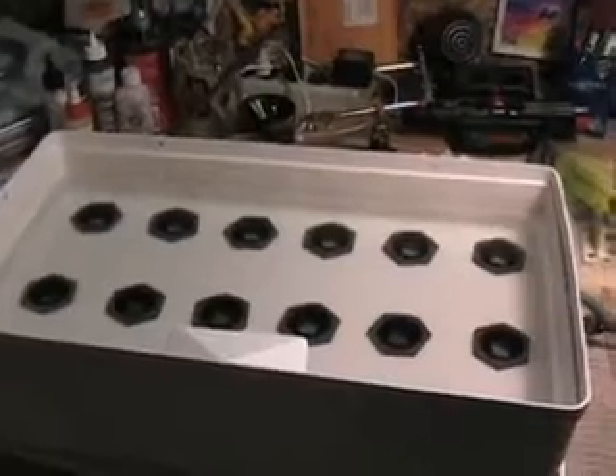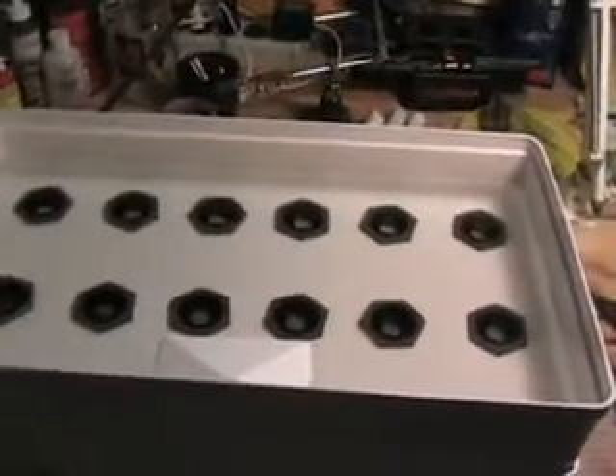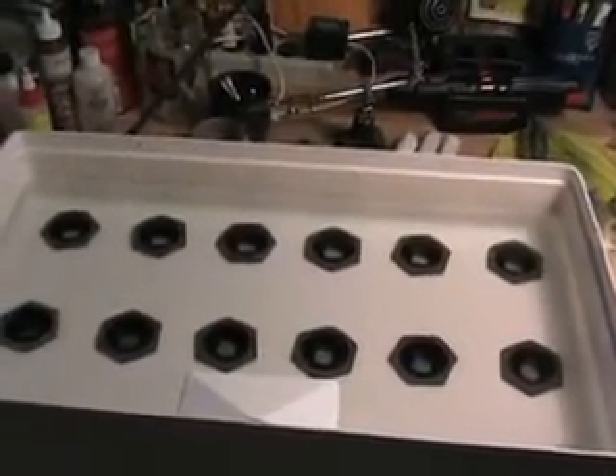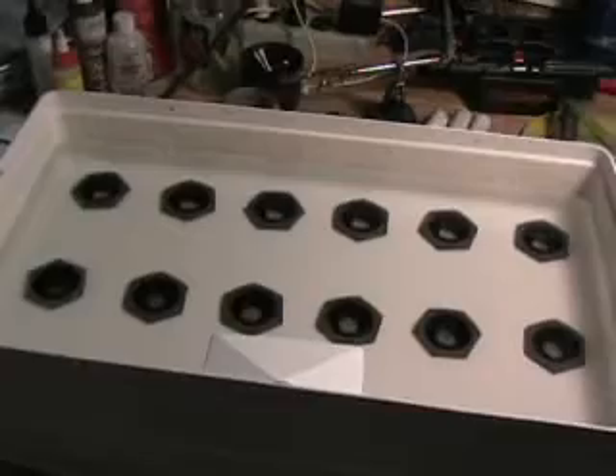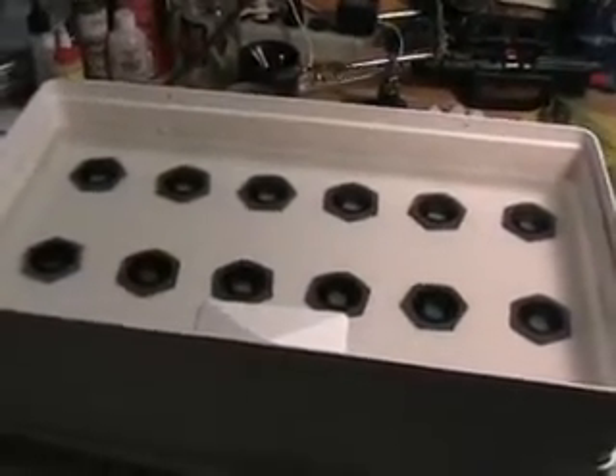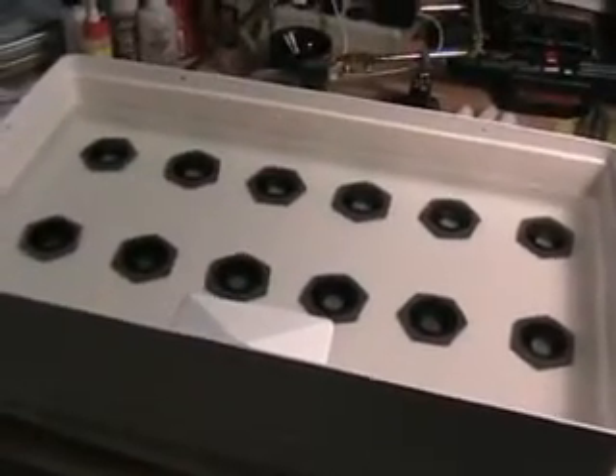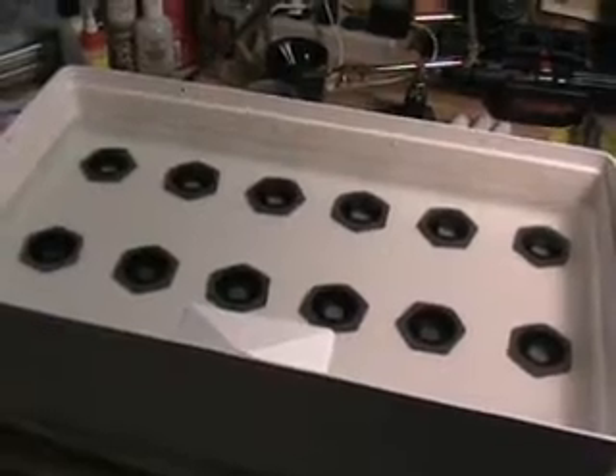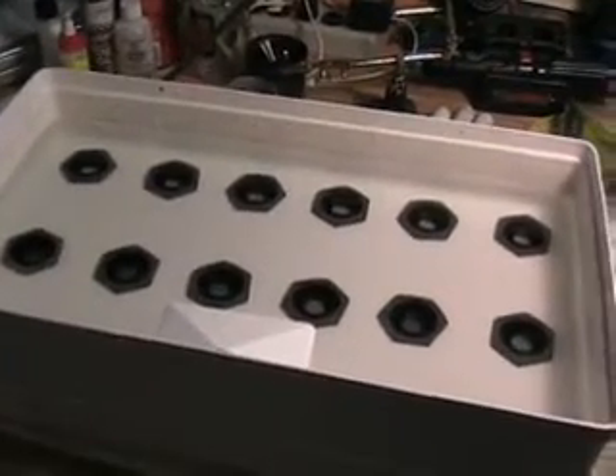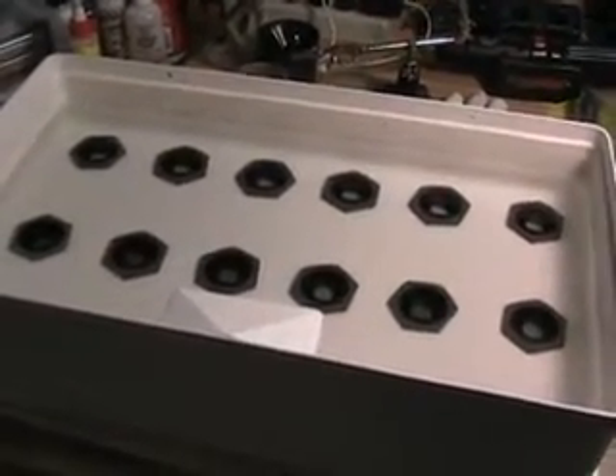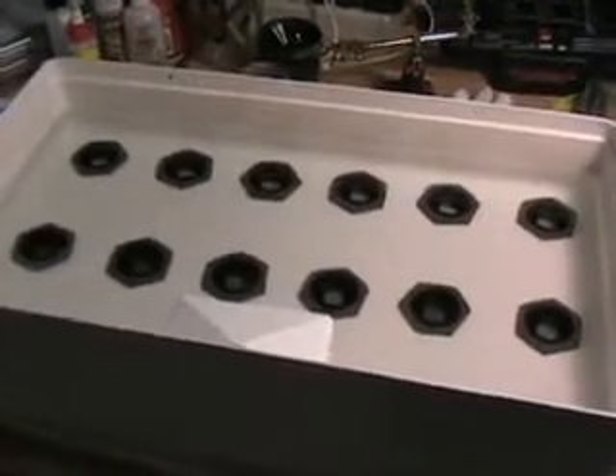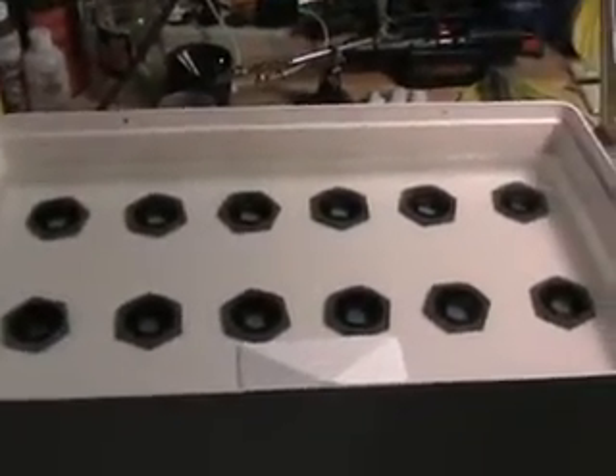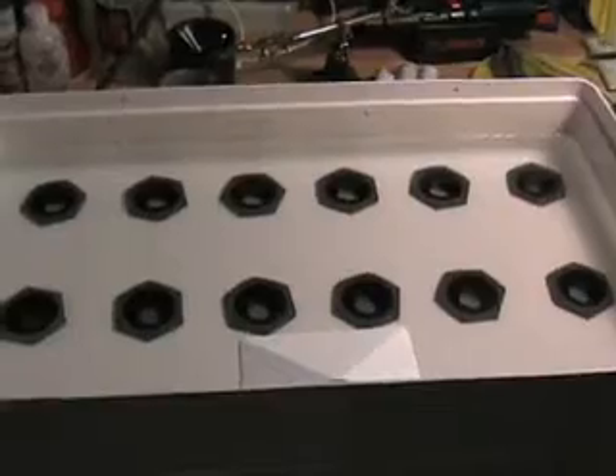It's a little bit better than an hour after we started, about 6:45. The pan's been cleaned, the transducer has been changed, we've leak checked it, reassembled the bottom pan, and filled it with water above the minimum cutoff. The minimum cutoff will stop operation if the water level is too low, and we want to make sure we have water in the tank. Never run the transducers without water over the top of them—they will fail.